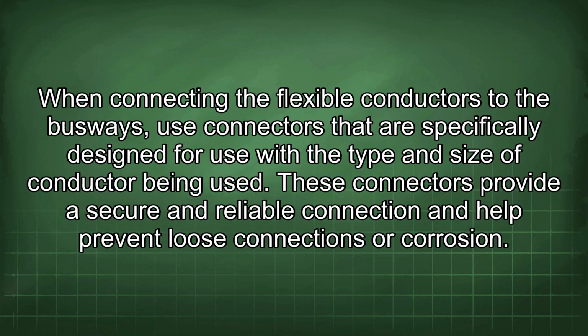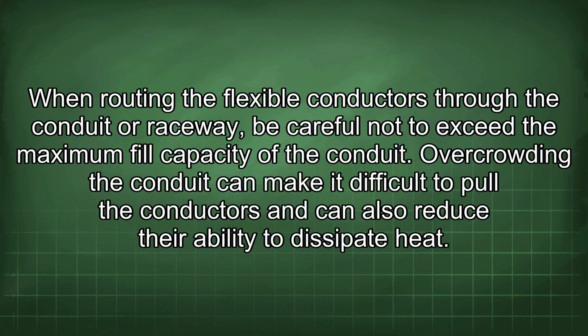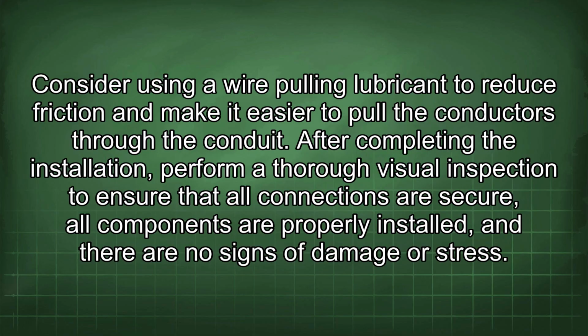When connecting the flexible conductors to the busways, use connectors that are specifically designed for use with the type and size of conductor being used. These connectors provide a secure and reliable connection and help prevent loose connections or corrosion. When routing the flexible conductors through the conduit or raceway, be careful not to exceed the maximum fill capacity of the conduit. Overcrowding the conduit can make it difficult to pull the conductors and can also reduce their ability to dissipate heat. Consider using a wire pulling lubricant to reduce friction and make it easier to pull the conductors through the conduit.